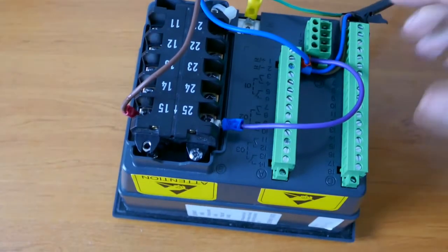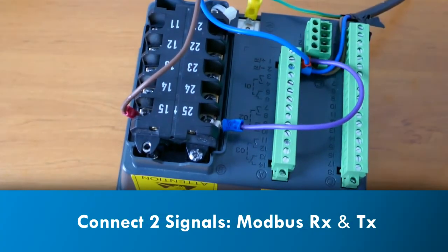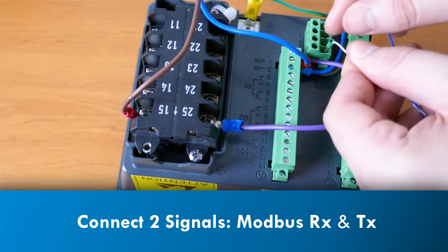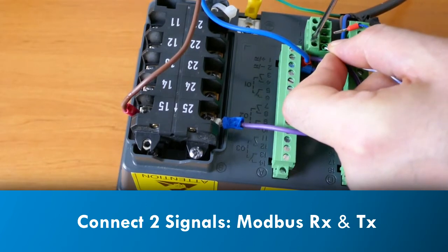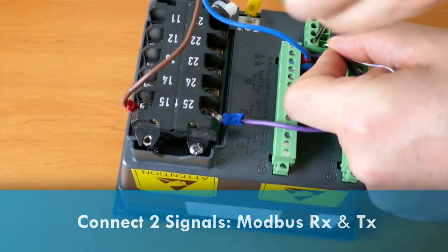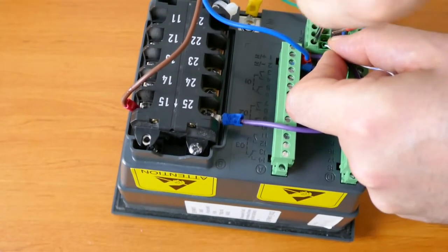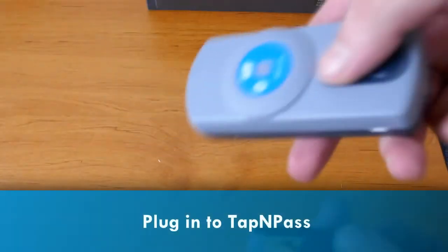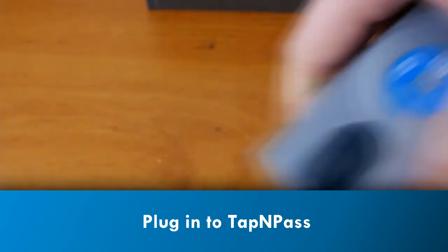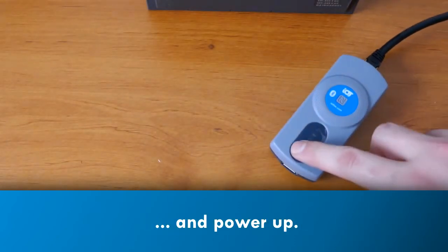Make the RXTX wire connections according to the equipment documentation. Note that inverting these connections will cause communications to fail, so we'll test the communications before we configure the TapNPass. Now, plug the cord into the RJ45 connector on TapNPass. Power up, and you're ready to test the connection.